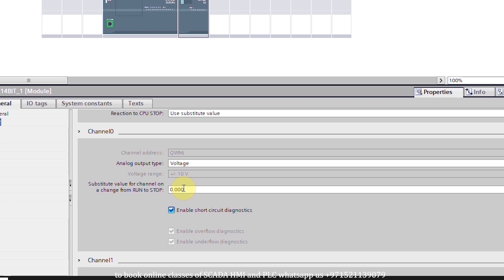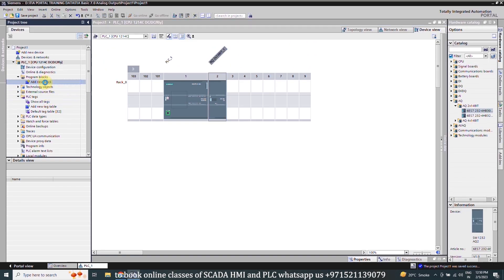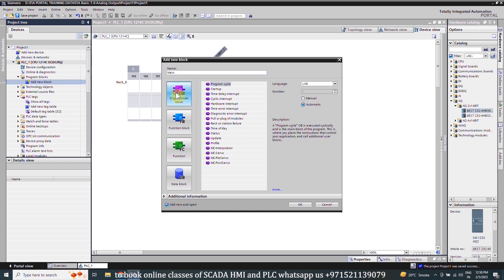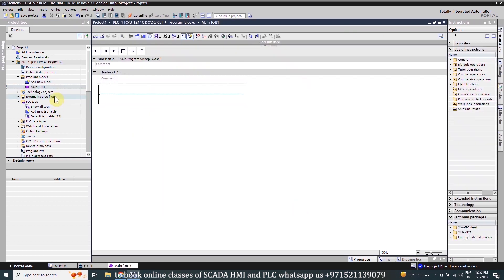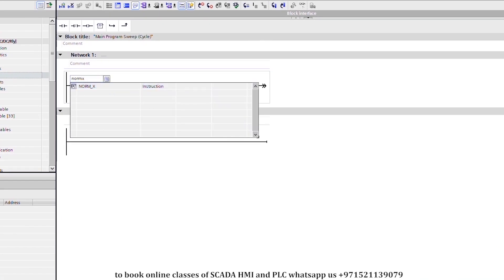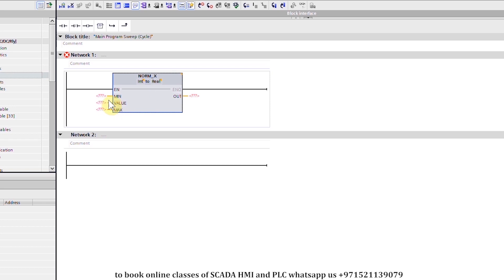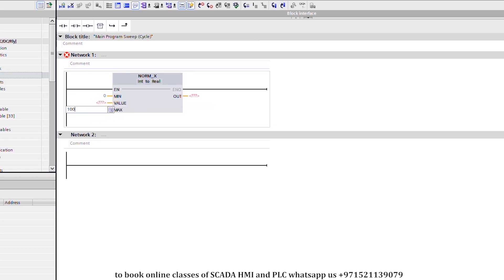Next we will add a new block — organization block one, OB1. We will add a block on it and search for the NORM_X instruction. We will select the NORM_X instruction, select INT data type for the input and REAL data type for the output. Put zero in the minimum, and in the maximum we will put one hundred.